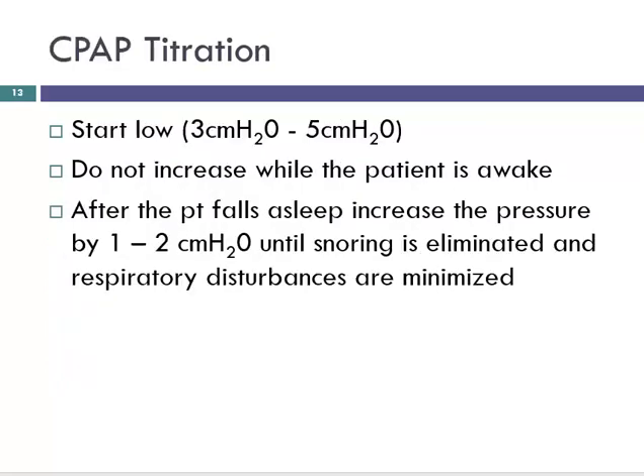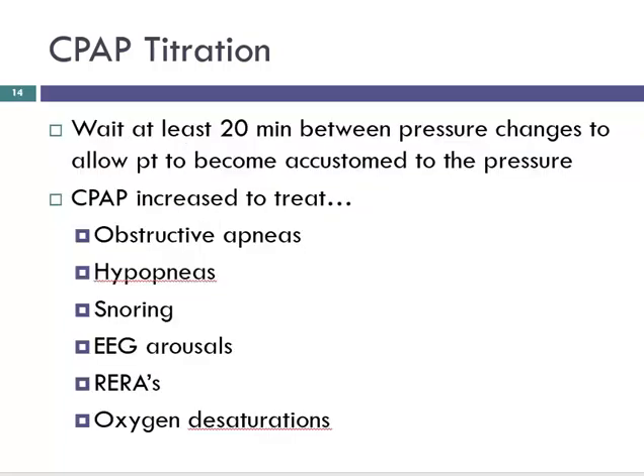Start low, and wait till the patient falls asleep to start changing the pressure, because we're titrating the pressure for things that happen while they're asleep, in increments of 2 centimeters of water pressure. So most patients I start around 5. I usually go as conservative as possible with my titrations, meaning I'll increase by 1, wait about 20 minutes, increase by 1, and see what happens.